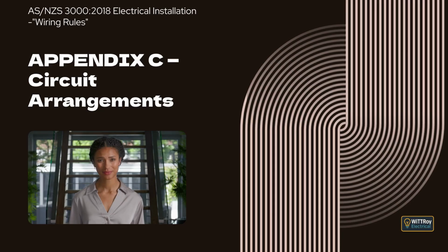Where this is not the case, the number of cables should be reduced to avoid excessive pulling tension or bending stress. This clause also explains that the calculation does not take account of grouping effects on current carrying capacity, temperature rise, or voltage drop, and that derating factors from ASNZS 3008 must be considered separately when assessing circuit suitability.